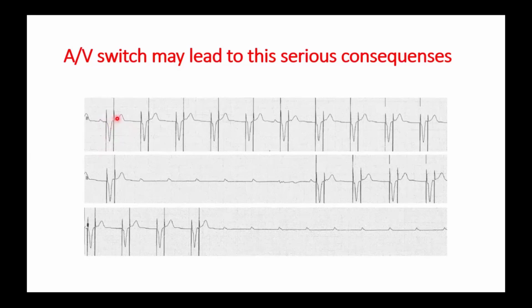So the second spike is the atrial spike, because this is the lead which is placed into the ventricular port. Exactly. What happens here is that the ventricular lead, which is placed in the atrial port, has sensed the P wave as if it is ventricular, because of the amplitude. So the pacemaker thinks, okay, this is higher than me, I'm not going to fire. But because it is the one firing the ventricle, it stopped firing, so the patient had this asystole.